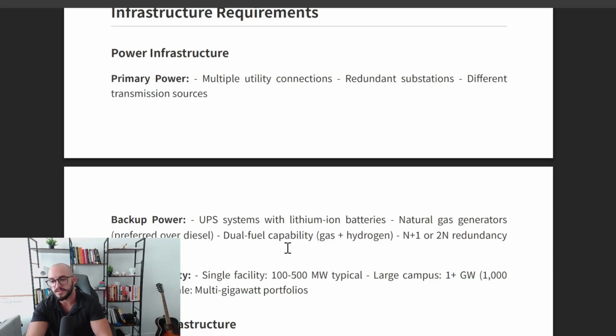Natural gas generators are usually preferred over diesel, because diesel can't just sit on site, after 6 months it degrades. Dual fuel capacity, like I said earlier, and N+1 or 2N redundancy configurations. That just means if it's a 500 megawatt site, they have 500 megawatts of power sitting ready as redundancy, so if the power source goes down, they have 500 megawatts behind it. That's what N+1 and 2N mean.